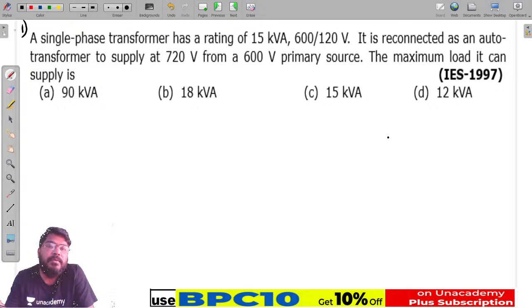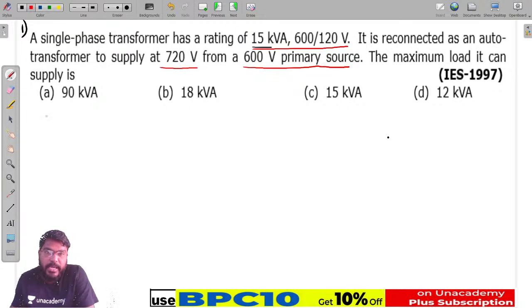A single phase transformer has a rating of 15 kVA, with voltage rating given as 600 upon 120 volts. It is a single phase transformer, reconnected as an auto transformer to supply at 720 volts from the 600 volts as primary. This is the rating of the two winding transformer, here given 15 kVA rating.